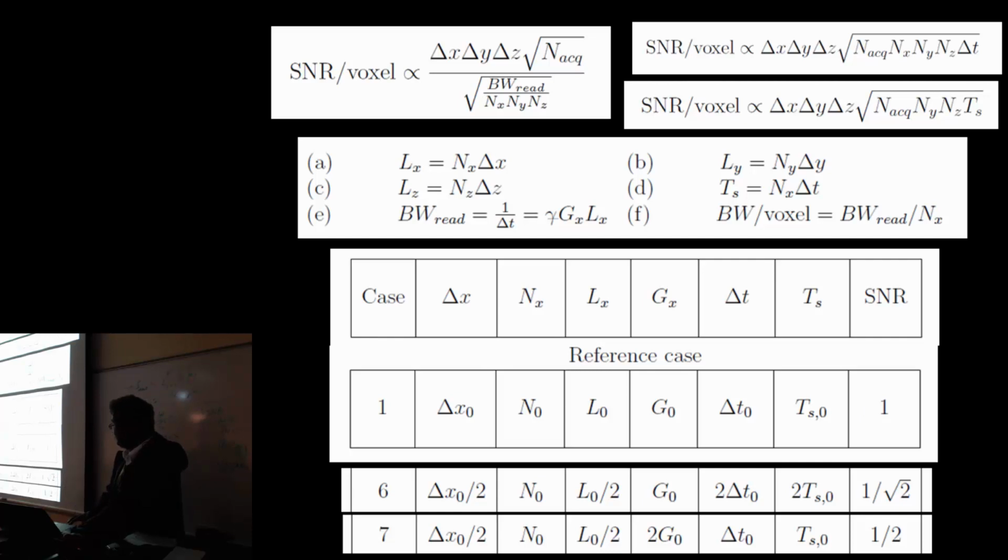So in this case I'm taking twice the sampling time, right? Let's say my sampling duration initially was 10 milliseconds, now it's 20 milliseconds. Now T2 star of the tissue is, let's say, about 25 milliseconds. Then your sampling duration is on the order of T2 star, so obviously you'll have a lot of filtering effects, right? And so you wouldn't want to do this.